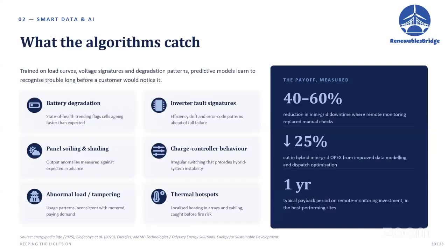So once you have the right AI tools in place, some of the most important factors that actually lead to failure are degradation of the batteries. Even if it's not lead acid but lithium ion, which can last for X amount of cycles, it's very important to track that degradation, especially depending on how it's charged and discharged, and deep discharge. All of that needs to be tracked. Also panel soiling and shading, which I talked about, you have information on that. The load - we've seen projects designed for X amount of megawatt hours, and then the consumption doubles or triples, and no one's tracking that.